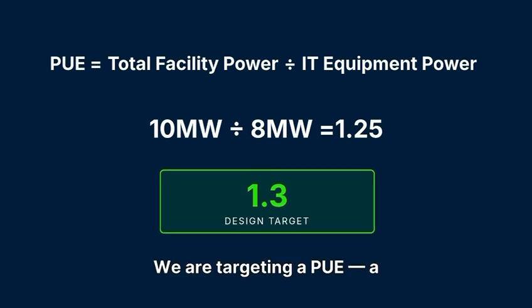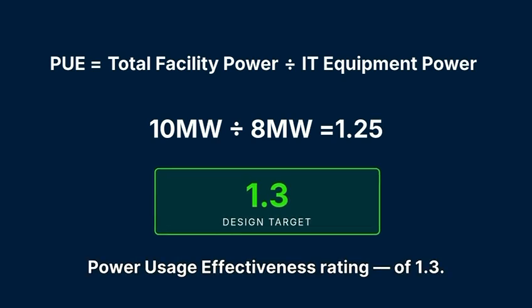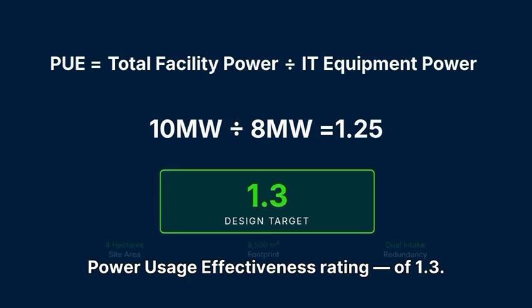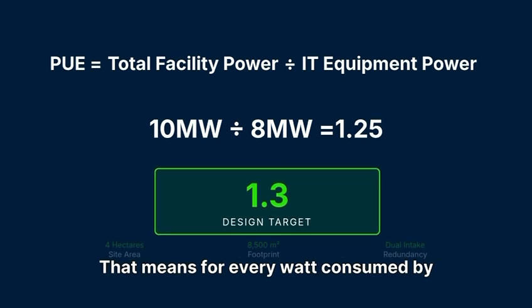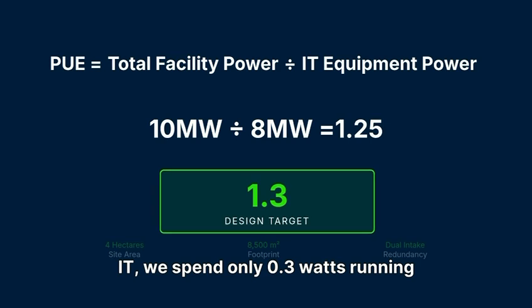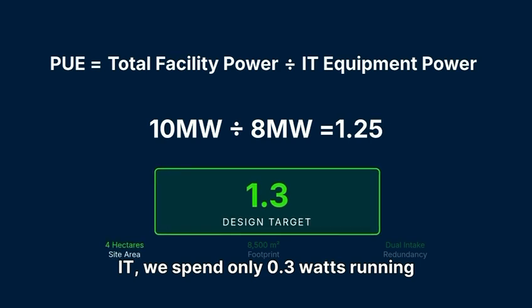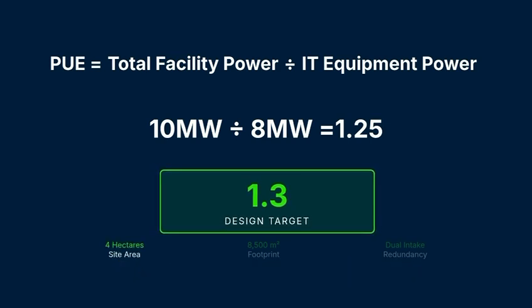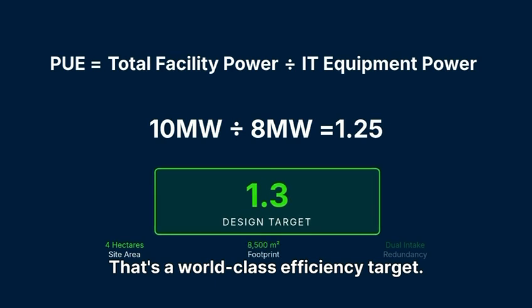We are targeting a PUE, a power usage effectiveness rating, of 1.3. That means for every watt consumed by IT, we spend only 0.3 watts running the building around it. That's a world-class efficiency target.